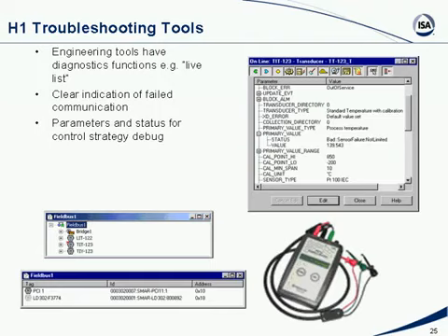You can click on the port icon in the software to see what the error rate is, the percentage of communication failures on the bus. If that's anywhere above 1%, you know you have a serious problem and need to fix it. If it's low, the bus is working all right. So this is good diagnostics to have available in the system.